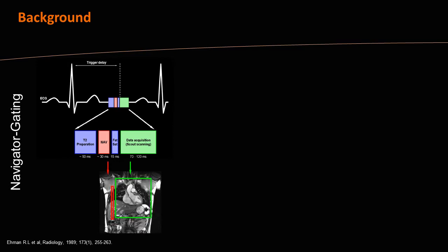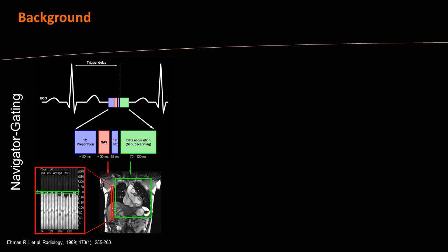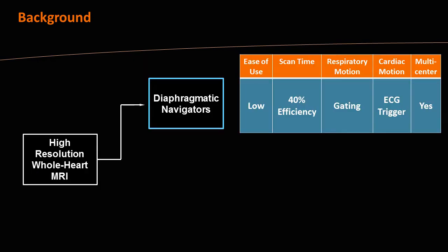At each cardiac cycle, not only is a certain amount of data acquired, but also an extra diaphragmatic navigator — an external acquisition at the liver-lung interface. This allows us to see at each heartbeat the position and displacement of the liver due to respiratory motion. An acceptance window is used so that only data acquired at a certain respiratory position, usually end expiration, are accepted; others are rejected and reacquired. The acceptance rate is quite low, so scan time is long with efficiency around 40%. Ease of use is not great, but this technique has been around for more than 20 years with large patient studies and multi-center trials.